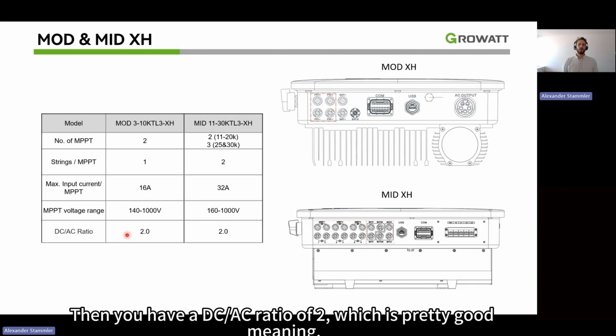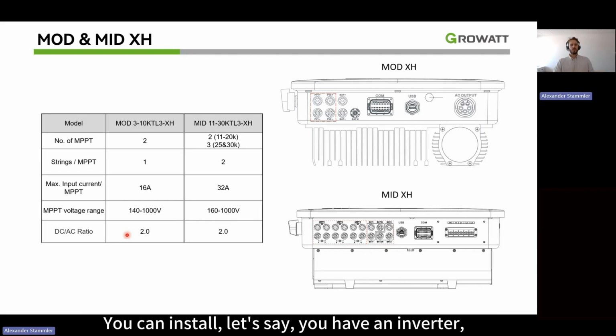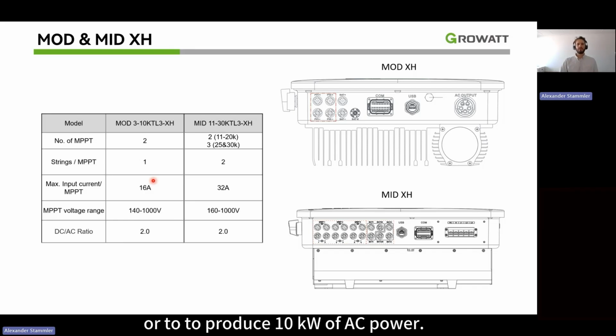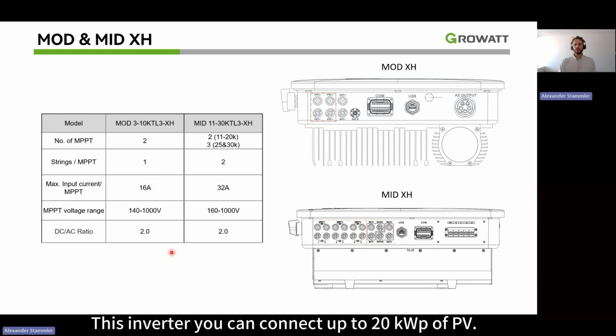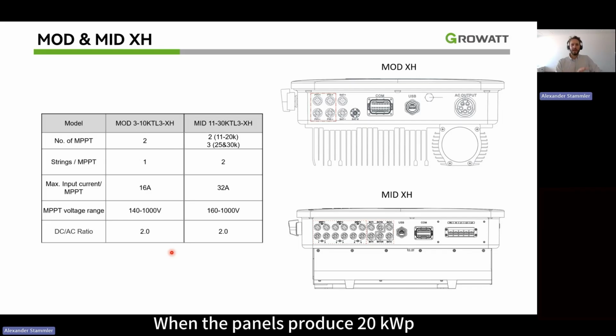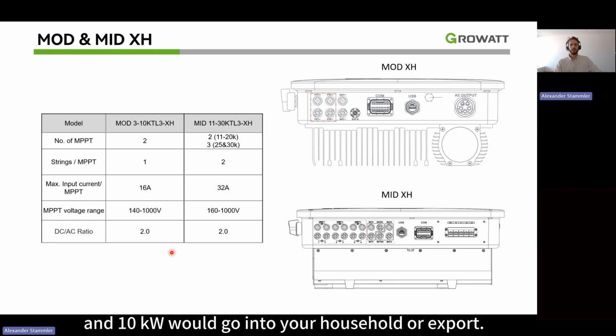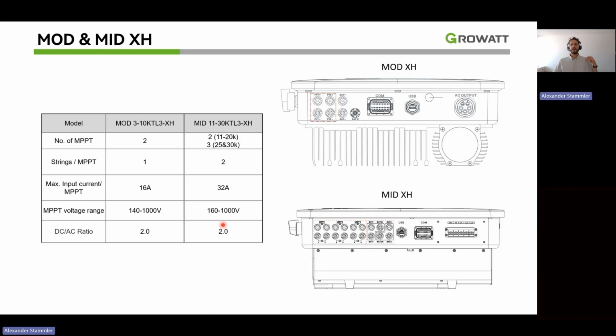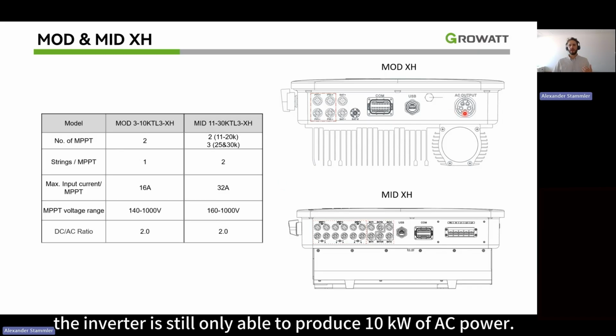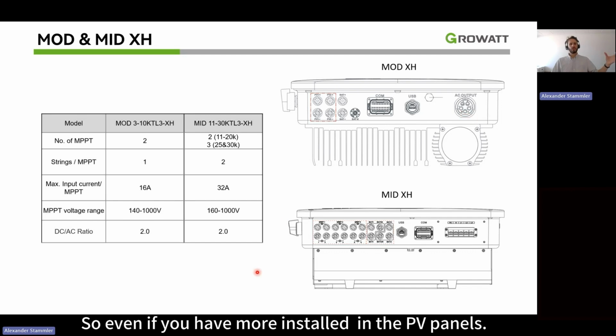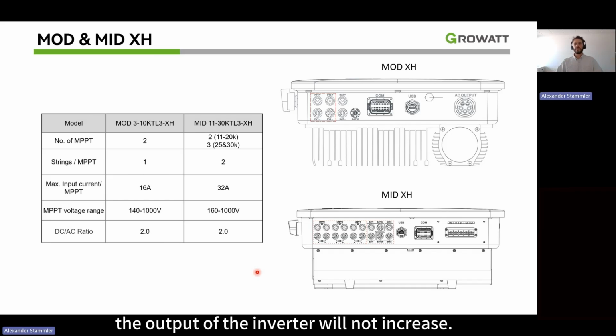Then you have a DC-AC ratio of 2, which is pretty good, meaning you can install, let's say you have a MOD 10K inverter, which is able to produce 10 kilowatt of AC power. This inverter, you can connect up to 20 kilowatt peak of PV. When the panels produce 20 kilowatt peak, then 10 kilowatt would go into the battery and 10 kilowatt would go into your household or export. Once the battery is full, the inverter is still only able to produce 10 kilowatt of AC power. So even if you have more PV panels installed, the output of the inverter will not increase.